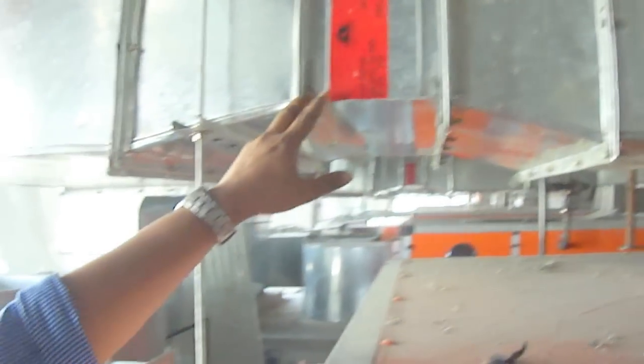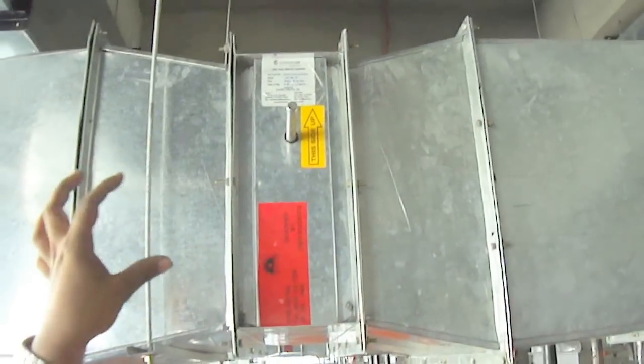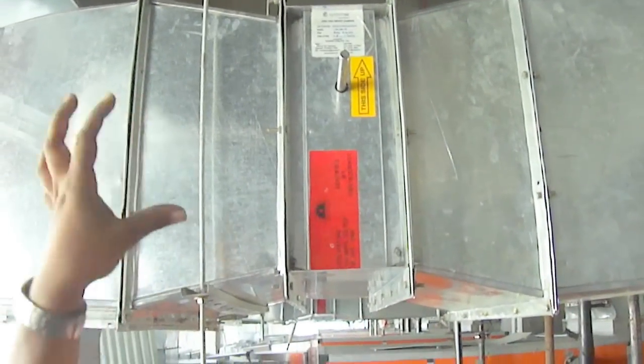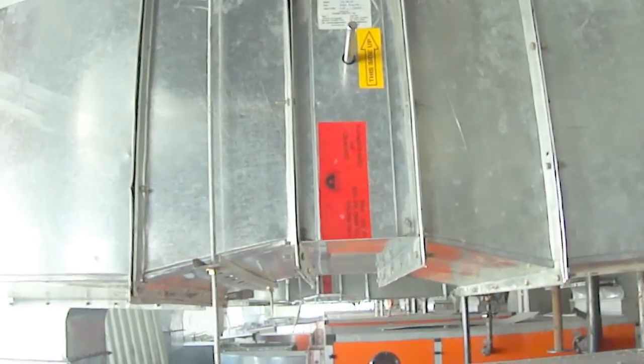5 ampere. Yes, very good. 5 ampere yet to complete. The motorized things or the controls are going to connect here. So why is 5 ampere required? With the return air, if you get hot air, this will restrict the supply. Whenever restriction is there, the AHU will trip. So it will stop the supply of air, so as not to spread the fire in case of fire. So in return, you'll get the 5 ampere as well as in supply. So in supply, need to trace.